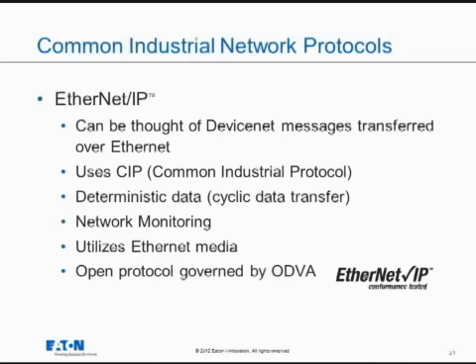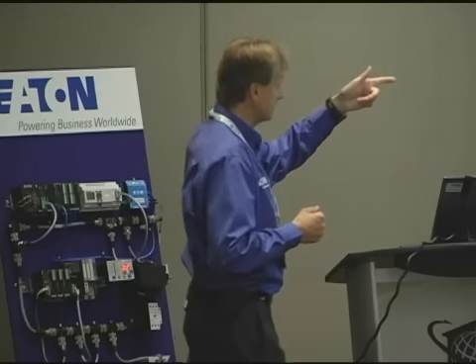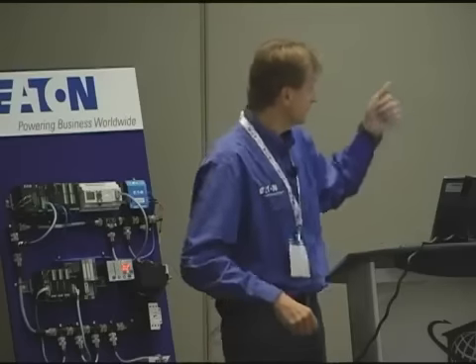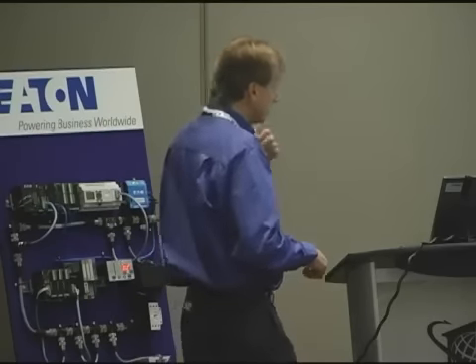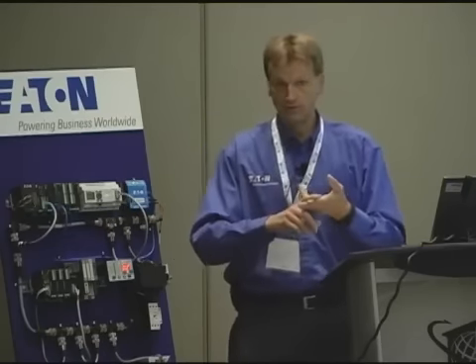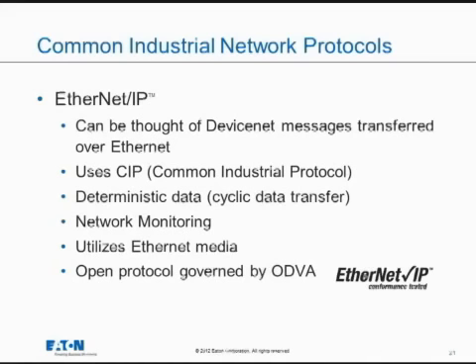EtherNet/IP can be thought of as DeviceNet messages transferred over Ethernet — similar to how Modbus TCP is Modbus over Ethernet. It also uses the Common Industrial Protocol (CIP). It has deterministic, cyclic data transfer with scheduled messaging, and includes network monitoring. It uses Ethernet media, allowing network expansion through routers and switches with multiple levels. It is also governed by ODVA, and there is a conformance tested logo for it.